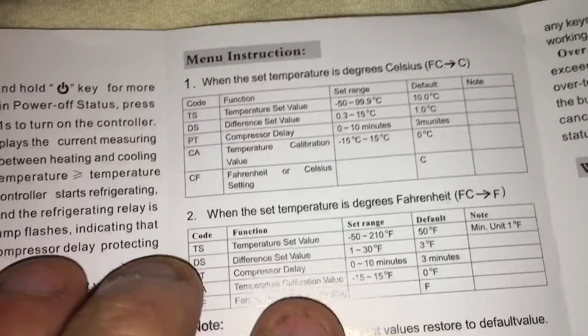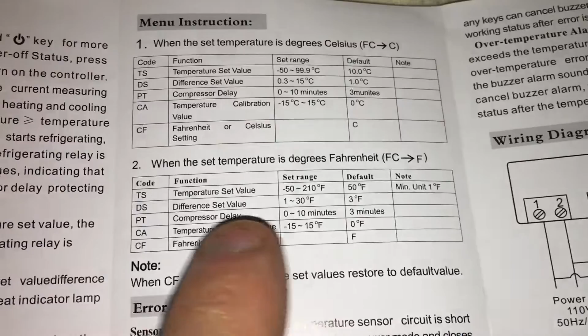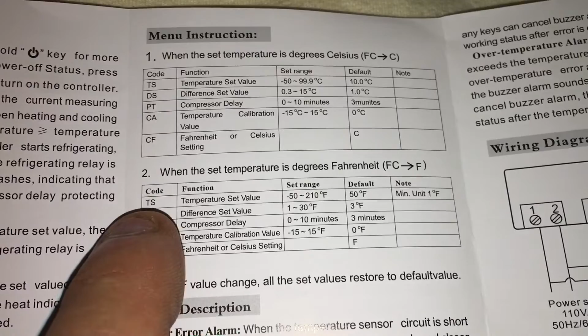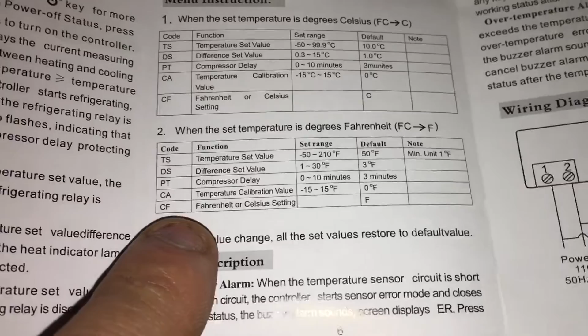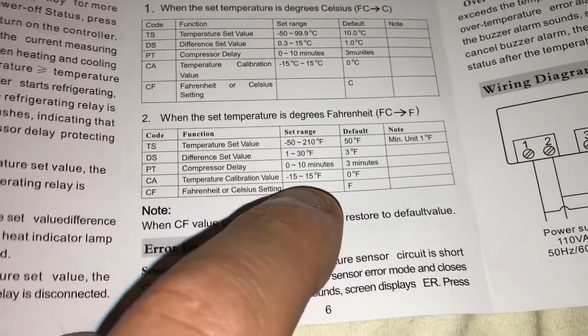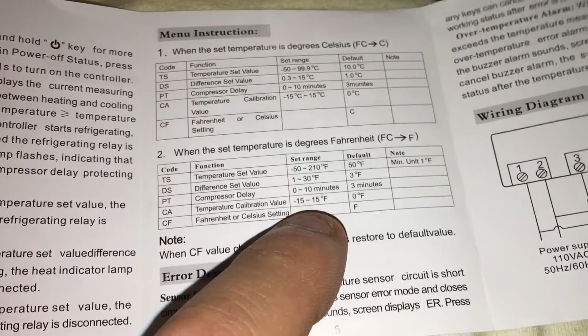So your TS is going to be your temperature set point, default of 50. I've got it set at 60 right now. Differential 1 to 30, default of 3. I've got it set for 10. Compressor delay, that's your 0 to 10 minute compressor protection. So PT for protection, TS for temperature set, DS for difference set. Your temperature calibration value, there's your calibration that I was talking about. So you could put in an offset of 1 degree if you wanted to calibrate it.